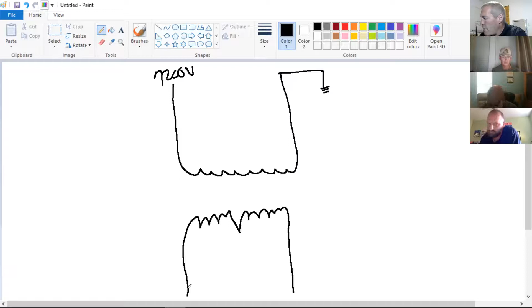Okay, that's my primary. I'll go ahead and put a voltage to it, 7,200 volts. This is going to be grounded. I'm going to do my secondary windings, 1, 2, 3, 4. If you were to picture this out here in the world, that's the primary bushing on one side of the top of the transformer, and that's the primary bushing on the other side of the top of the transformer. Here are the secondary lugs on the transformer.